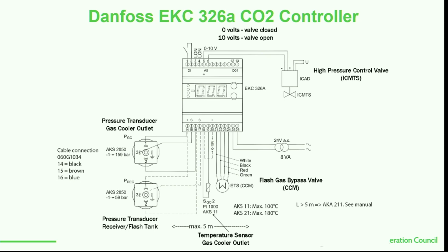Because if we have 1,500 pounds in the gas cooler, and upon a power failure, if we don't shut that valve, we're going to send that flash tank to Jesus. The pressure's going to go all the way up, and essentially have a relief event. You could get higher than 600, 650, and if you exceed 600, now we're going to cover later, it's going to shut off and I won't be able to restart it until I bring that pressure down. Correct. Once I exceed 600 PSI. Good question. All right, phase loss monitor, inputs.